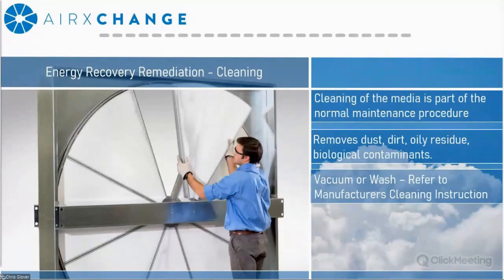The benefit of that is it allows you to really get a good deep clean of the device. So you basically introduce the segment and you submerge it in a soapy solution. This allows that soapy solution, detergent, to fully penetrate the heat exchange media and really loosen up anything that's accrued on that surface over time. And the other benefit of washing it that way is you're washing it outside the HVAC cabinet, so you don't run the risk of introducing any potential contaminant into the airstream.